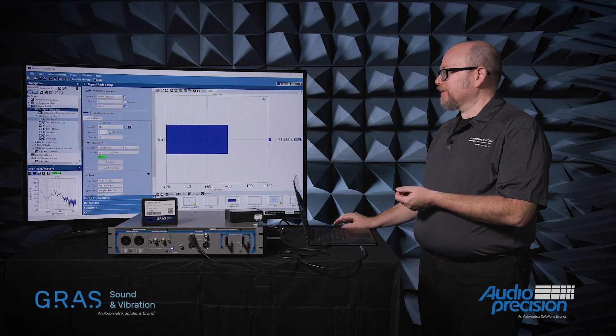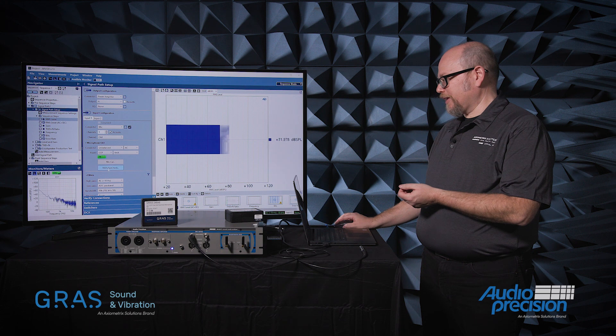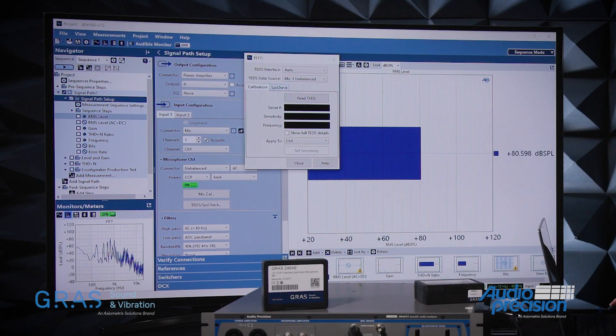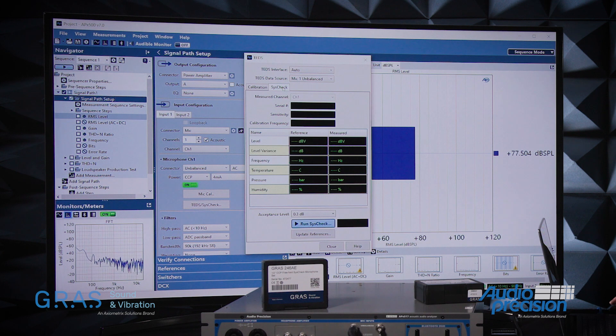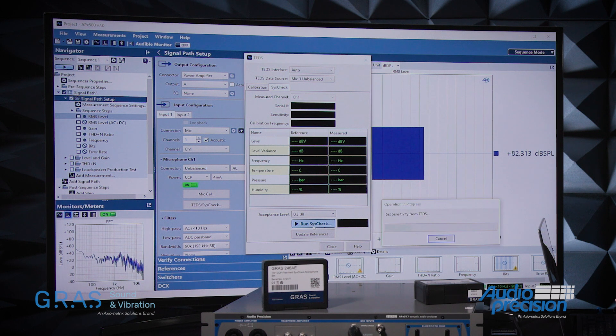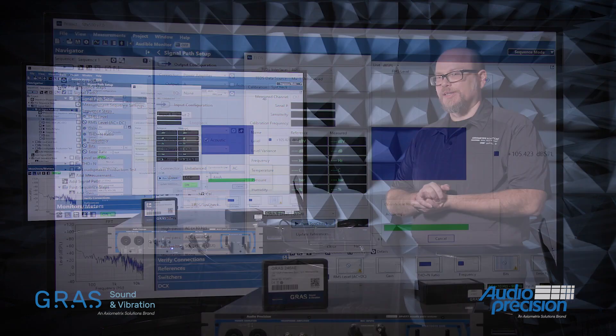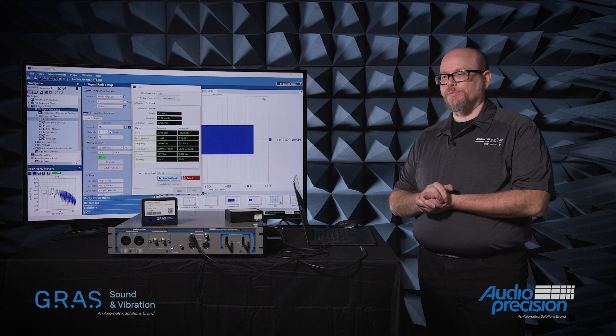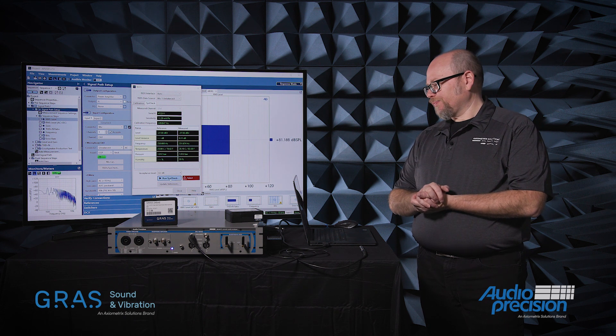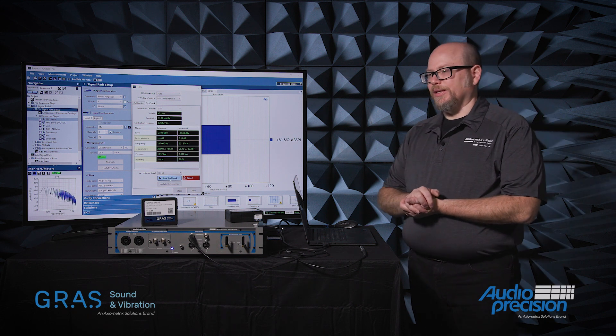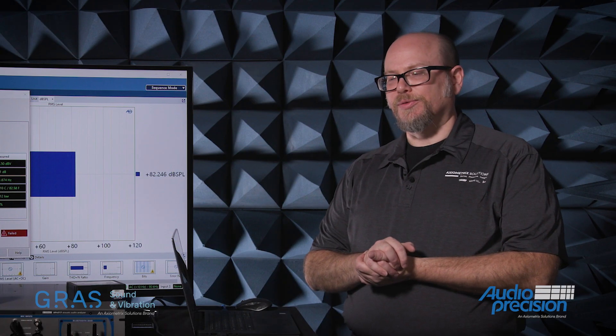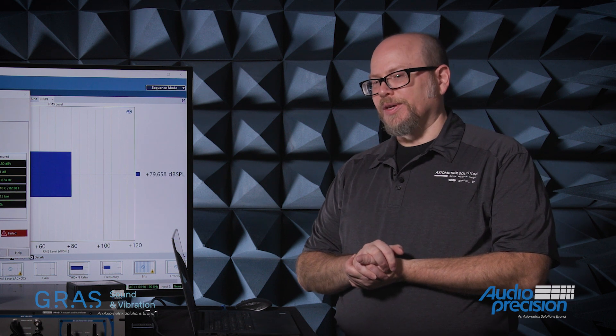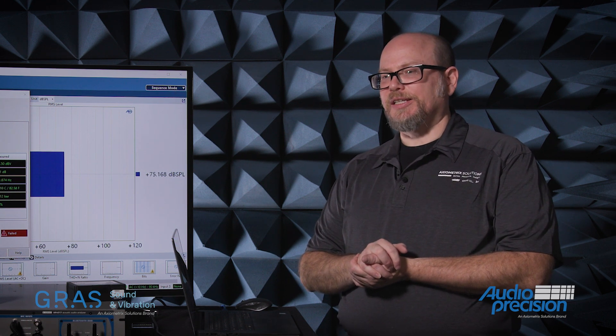If I go in the APX500 software into my TEDS SysCheck dialog, I'll select the SysCheck tab and select Run SysCheck. Unlike just reading TEDS data, this is an active process. There is actually a signal generator embedded in the preamplifier body of the microphone. That signal generator is in parallel with the output of the capacitor, or the diaphragm, of the microphone, and we actually sense any deviation in sensitivity.